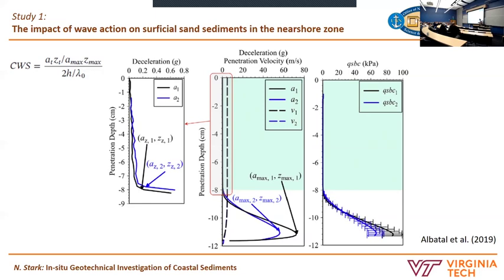So we get the force, and from the force we consider the area of loading from our geometry, and then we get practically the load or the bearing capacity. That leaves us with the fact that our penetrometer is slowing down, in this case from about 5 meters per second to a stop, and we know that soils are actually strain rate dependent. Imagine you have a clay and you try to hit it really hard, it may hurt your fist and it feels much harder. But if you poke it really slowly, then clay is really soft. This is strain rate behavior. So your strength actually depends on how quickly you're straining the soil, and the same happens to the penetrometer.